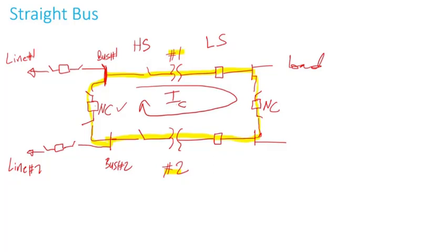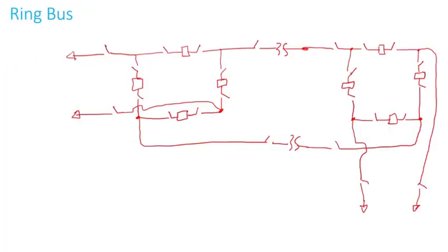In a previous video — part four — I showed how to calculate that circulating current. It's important when you have two transformers connected through straight buses, with the high side tied through a normally closed breaker and the low side also tied through a normally closed breaker, to make sure the transformers are not going to cause any circulating current.